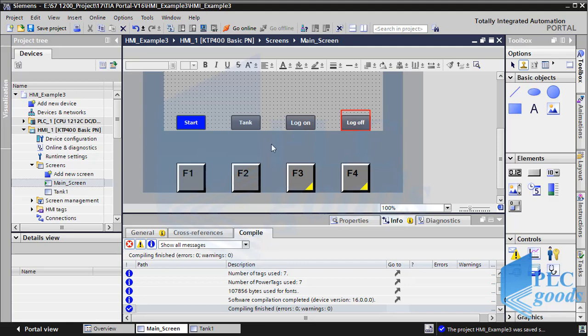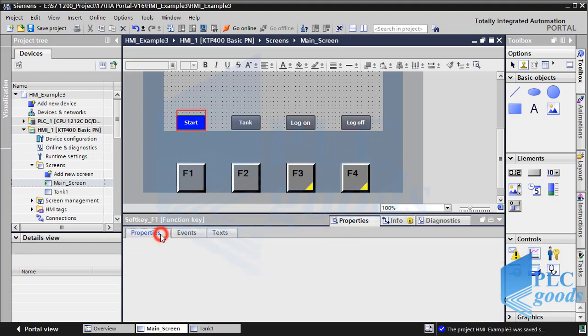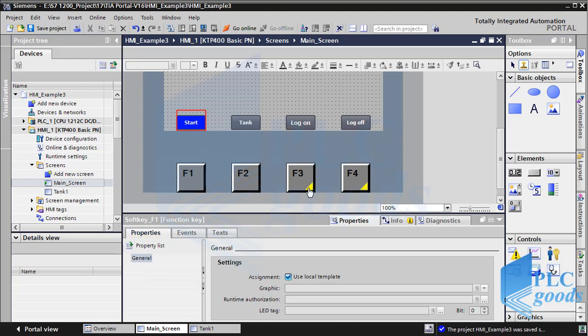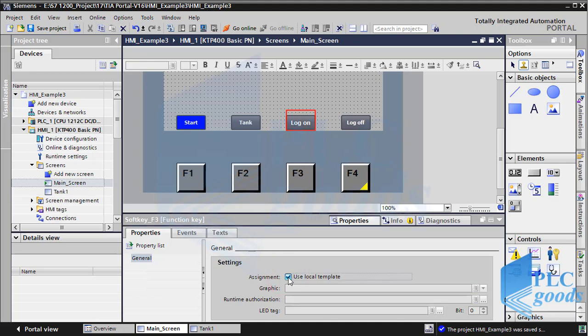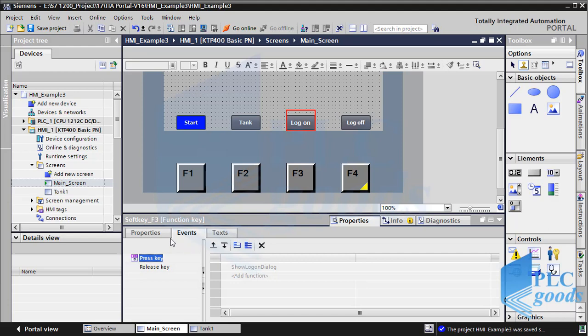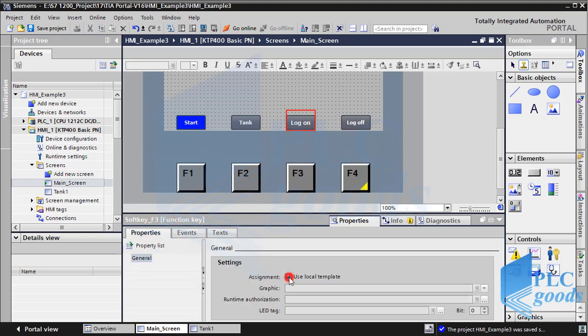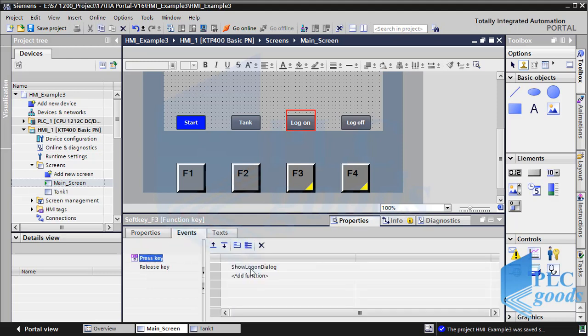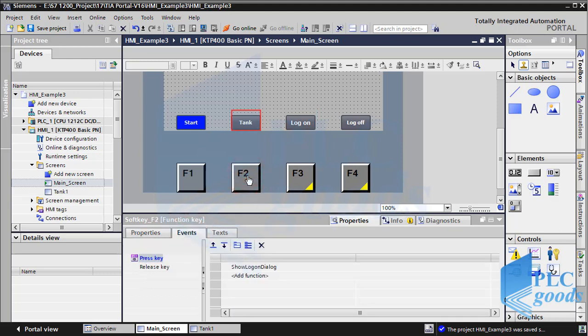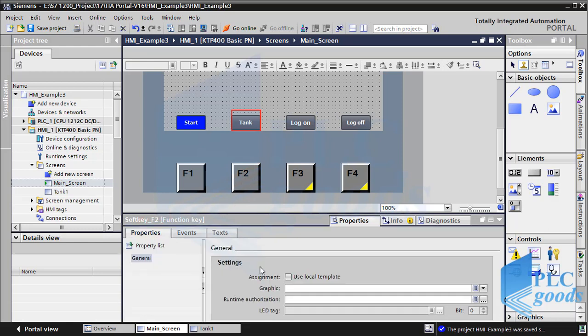On the other side we have global assignment — in this state, function keys will do one task in all HMI screens. Now let's use F2 to open the tank screen and F1 to open the start screen. First, activate the 'use local template' for F1. As you see, for F3 this ability is inactive; otherwise its local function will be inactive and it will use the global function. Let me go back to the local assignment state for F3, and activate 'use local template' for F2.